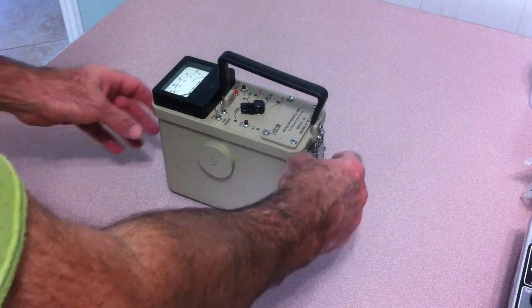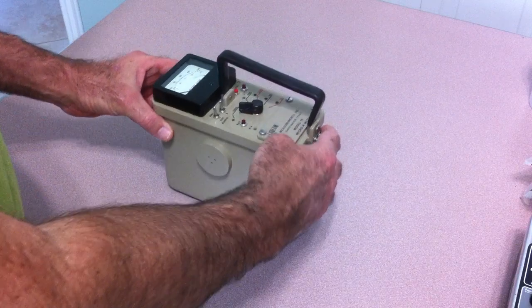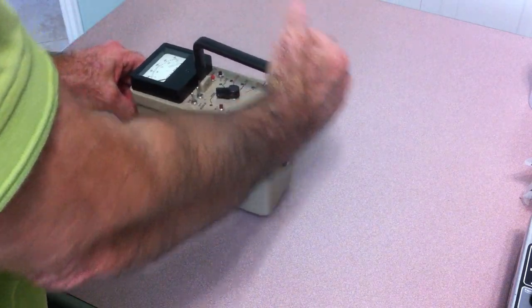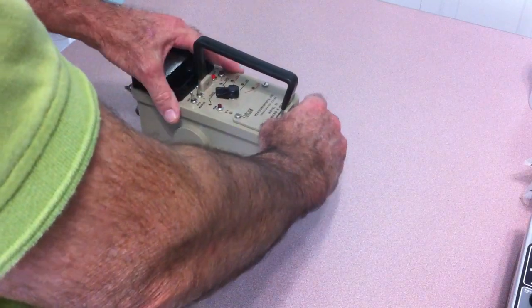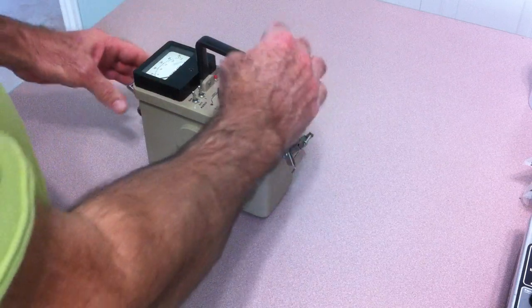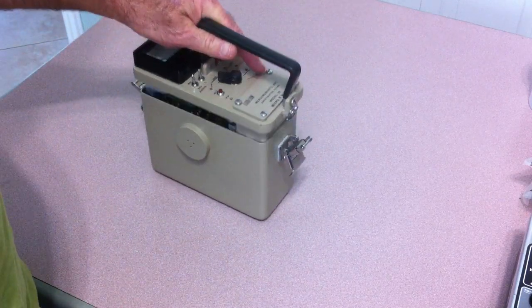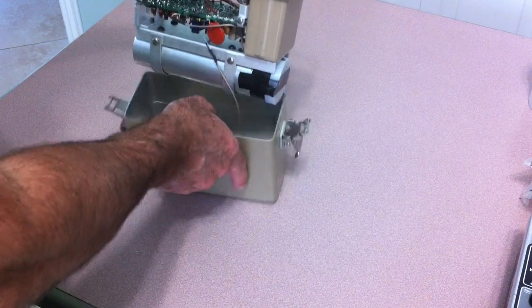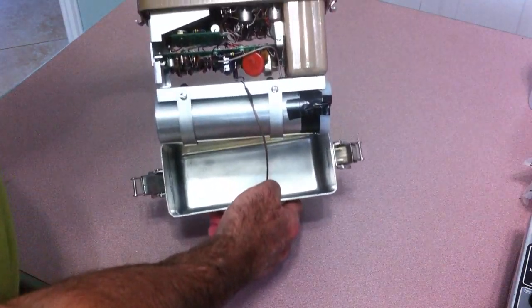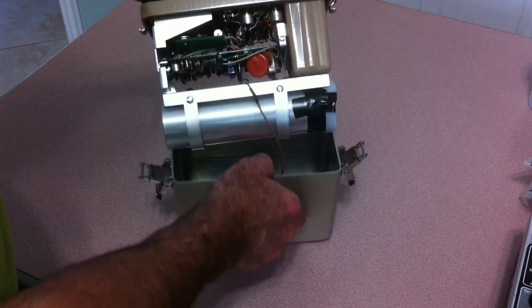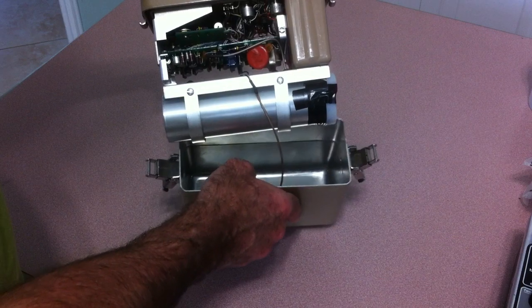It came in with a damaged scintillator crystal and with the typical decals, stickers, scrapes, and dirtiness found on these things when they're used. The meter was in excellent shape mechanically other than the sodium iodide crystal being melted away due to humidity over the years. That'll happen with these particular units since the probes installed by Ludlum are not fully sealed.